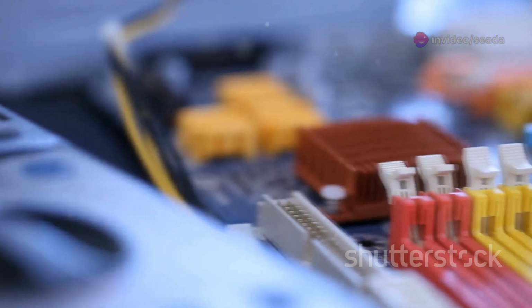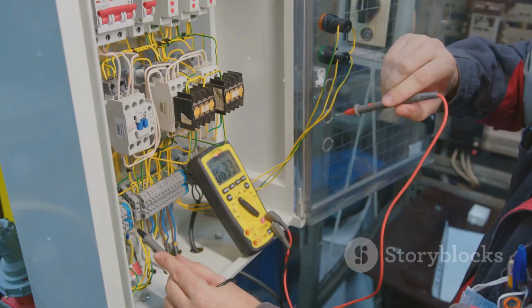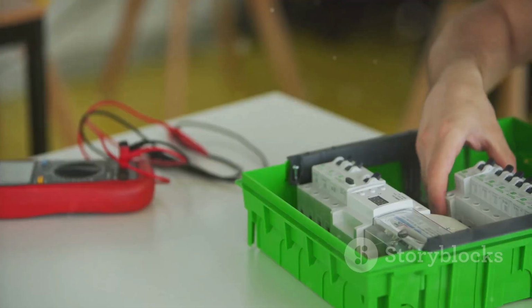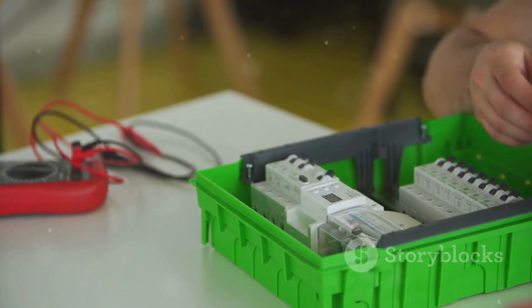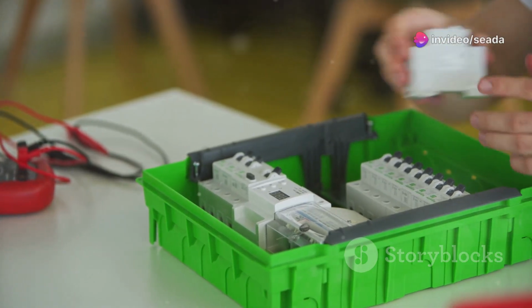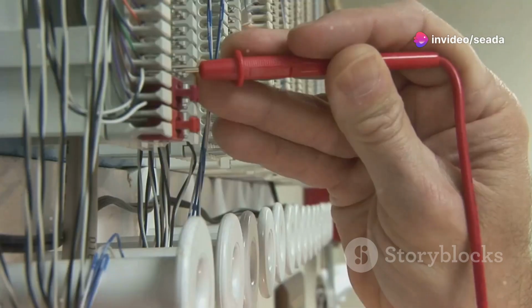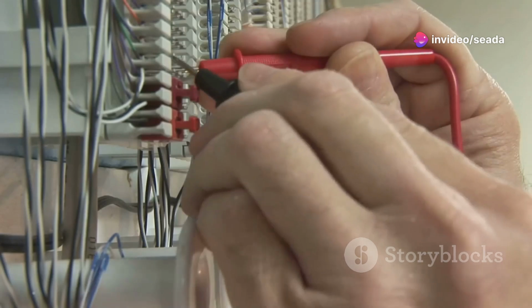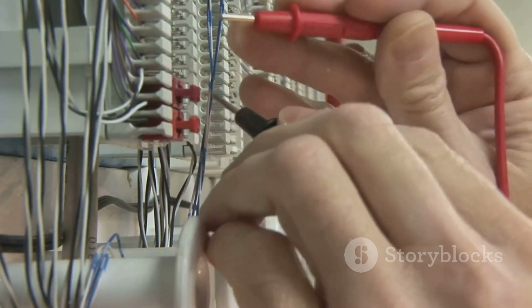With power off, switch to continuity mode. This setting lets you check for shorts or breaks in the wiring. Disconnect the circuit's live and neutral wires at the consumer unit. This prevents false readings from other connected circuits. Touch the probes to the ends. If the meter beeps, there's a short circuit. The beep is your signal that current can flow where it shouldn't.